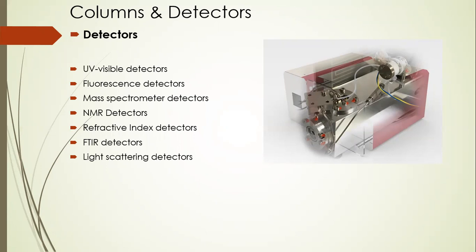In case of mass spectrometer detectors, these enable the analyte to be detected and its structure determined simultaneously. Analytes may be detected by total ion current (TIC) or selected ion monitoring (SIM). An advantage of mass spectrometry detection is that it affords a mechanism for identification of overlapping peaks. So these are the three most important detectors used in an HPLC system.